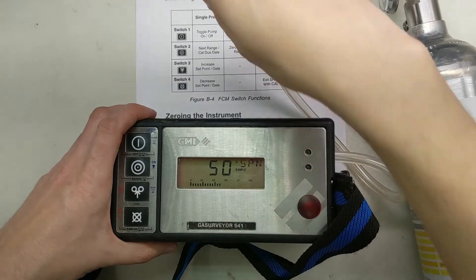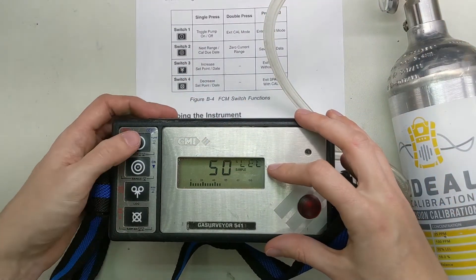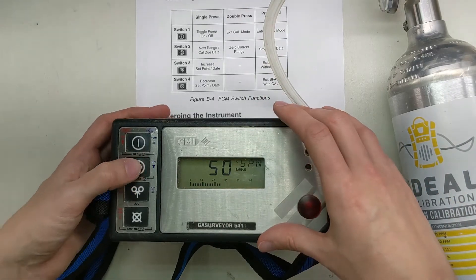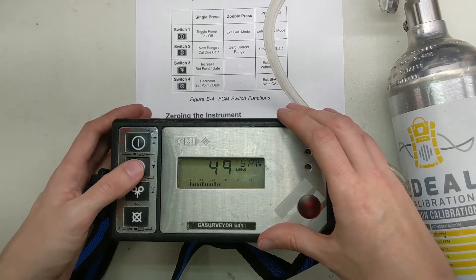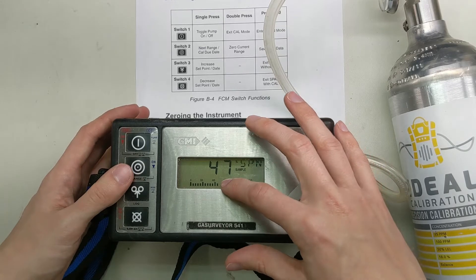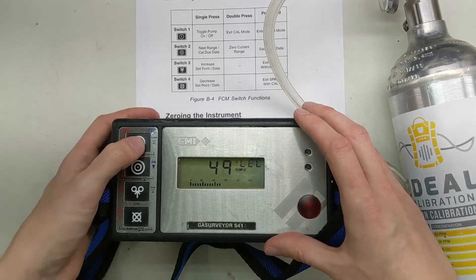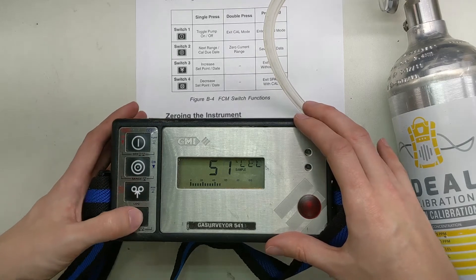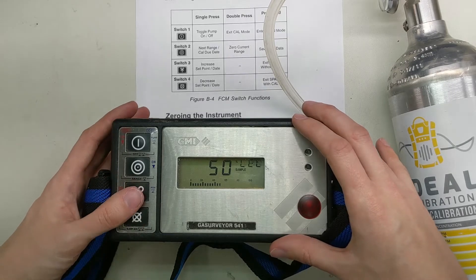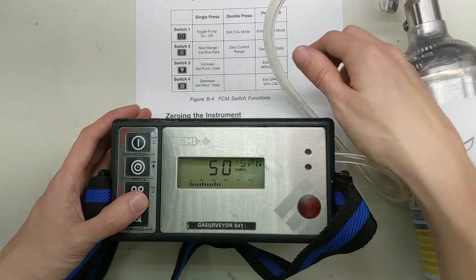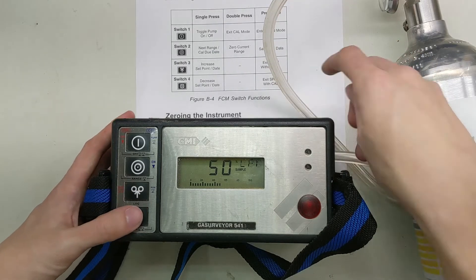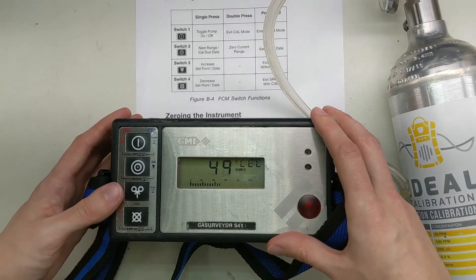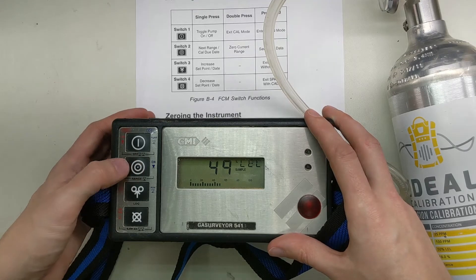We've got our gas on here and we're in span mode for the LEL sensor right now. These buttons up and down will take what it expects up and down. So if you have a different cal gas blend, you can use that here. What we're going to do is exit span with Cal. We're going to press and hold the switch four. Good deal. Now we're going to move to the next one.